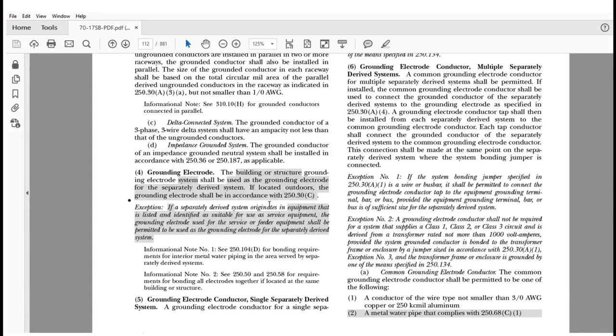Well, that was removed, and basically it says the building or structural grounding electrode system shall be used as the grounding electrode for the separately derived system, period. So you no longer have item 1 and item 2, which were grounding electrodes the way they stated it, and then they had to be used. The significance also here is it did reiterate that the water piping and the structural steel framing, as covered in 250.68(C)(1) and (2), were in the previous code, and they're being recognized as conductors to actually extend that grounding electrode connection.